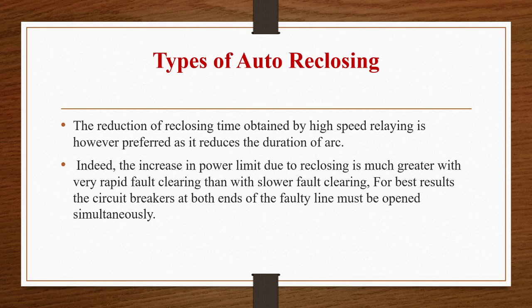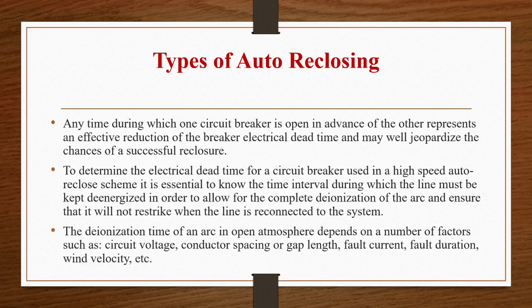Indeed, the increase in power limit due to reclosing is much greater with rapid fault clearing than with slower fault clearing. For best results, the circuit breakers at both the ends of the faulty line must be opened simultaneously. So any time during which one circuit breaker is open in advance of the other will represent an effective reduction of the breaker electrical dead time and may well jeopardize the chances of a successful reclosure.